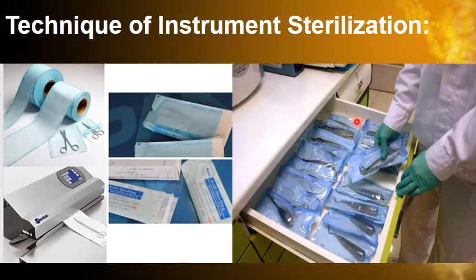When I arrange them, I will arrange them side by side. I will not put them one above the other. Why? Especially the surgical instruments have sharp points. If I stack the pouches one above the other, I may have a puncture of the pouch and I will lose all the sterilization. So I will arrange them side by side.